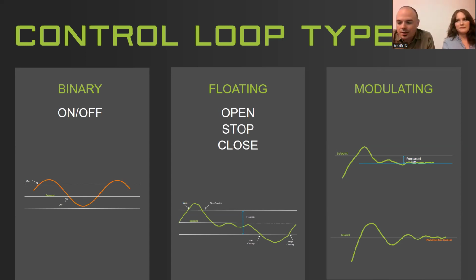Modulating I think of as a lot more of a direct correlation between the output percentage of the loop and what the physical device is doing. So going back to our chill water valve, if it took a modulating command, it's probably looking for something like a 0 to 10 volt DC signal, and it's looking for that voltage to be persistent - there's no time basis for this. You'll also see things like 4 to 20 milliamps, 2 to 10 volts, 1 to 5 volts, but for simplicity let's just stick with the 0 to 10 volt application.